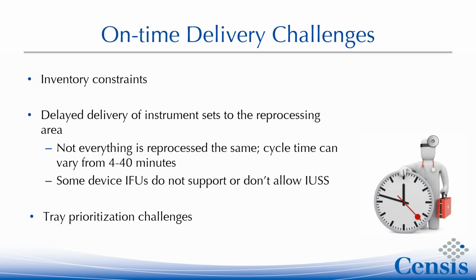Another challenge relates to expectations around how fast things can be reprocessed. Sterilization times can vary from 4 to 40 minutes, and for certain items, the go-to shortcut—immediate-use steam sterilization—isn't an option based on manufacturer's instructions for use. So when evaluating root causes of instruments not getting to the OR on time, it's important to remember that not all assets are reprocessed the same way.